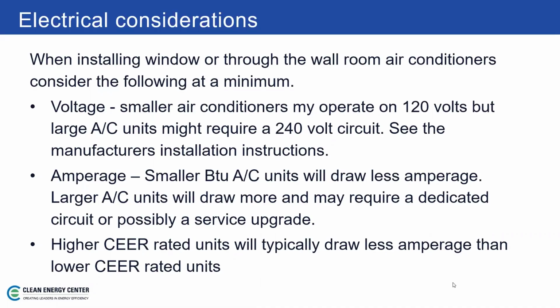Okay, just a few considerations when we're talking about electrical. I know that question came up before. When you're installing, the split system stuff is already going to be taken care of, and your HVAC contractors are well aware of the electrical needs and the sizing. But when it comes to window or through-the-wall room air conditioners, at a minimum you want to think about voltage. Small air conditioners may operate on 120 volts, but a large unit may require a 240 volt circuit. Again, you'll need to see what the manufacturer installation instructions require as far as amperage for your circuit or your overcurrent device. And then amperage is the other big consideration.